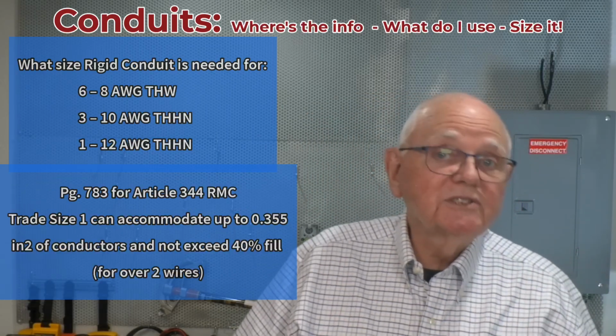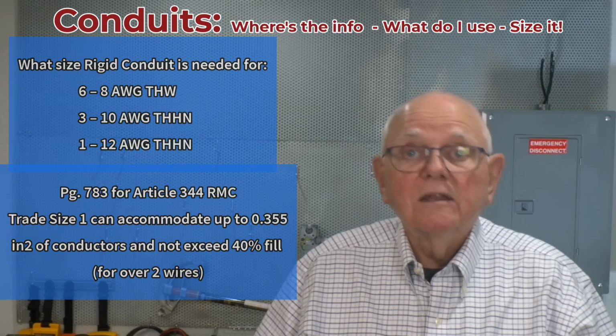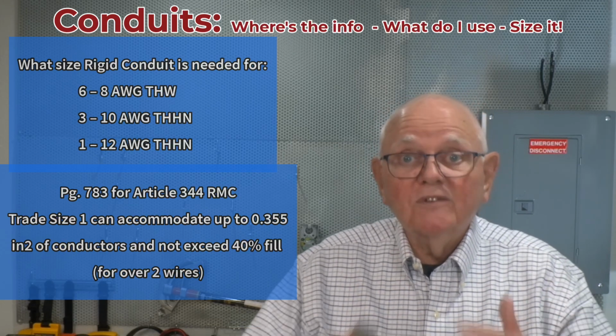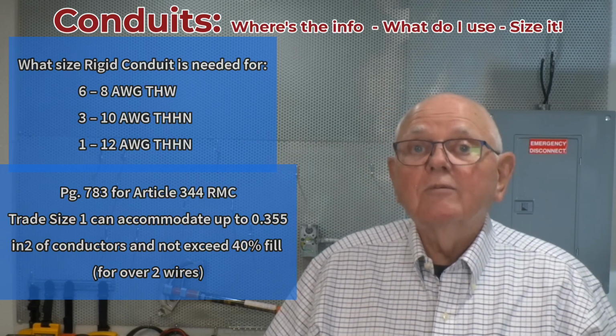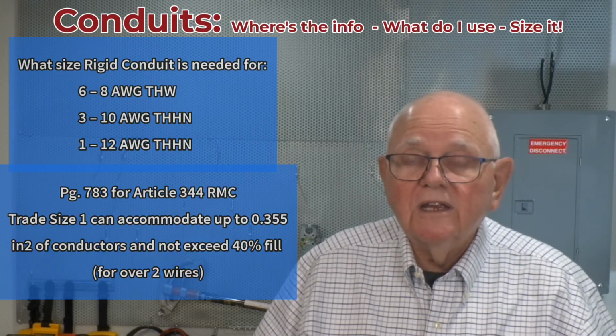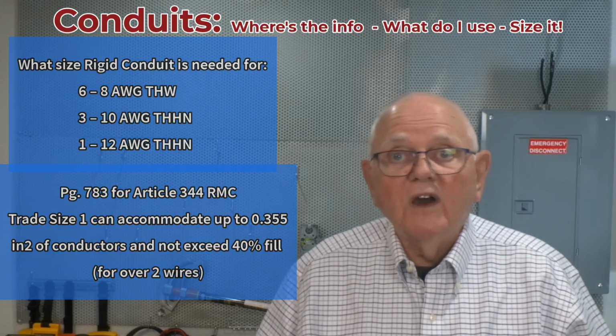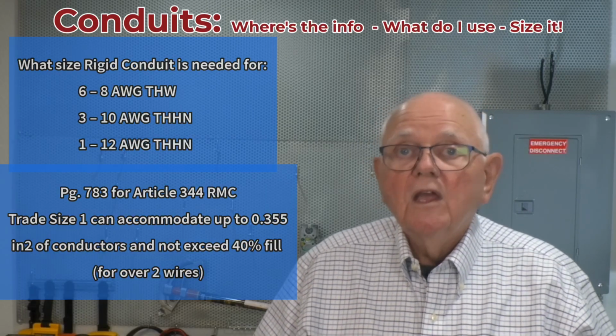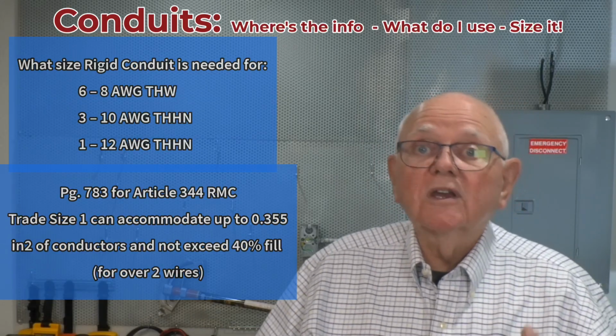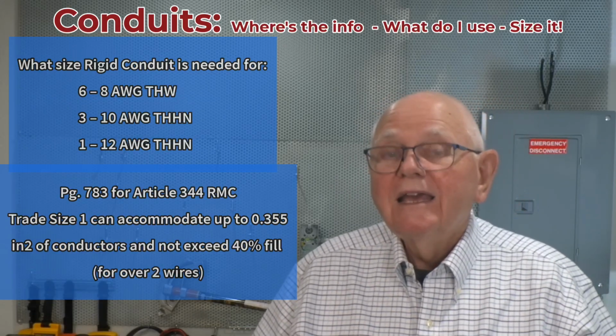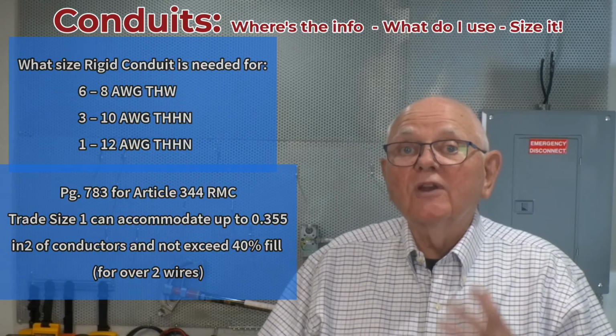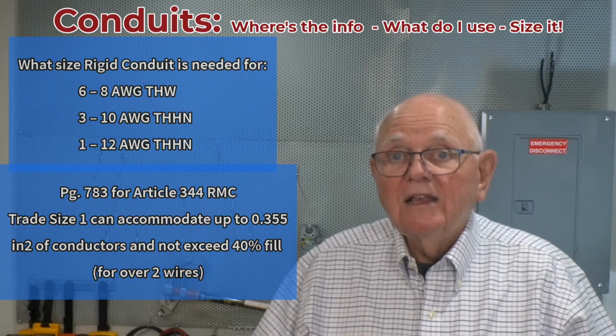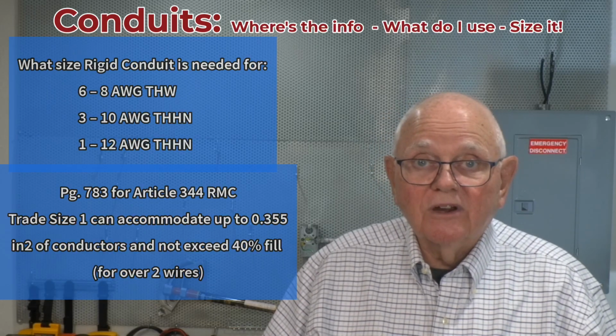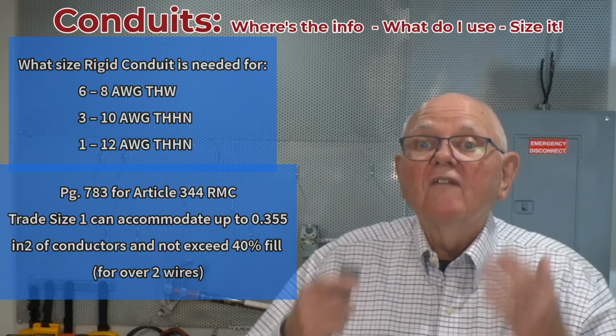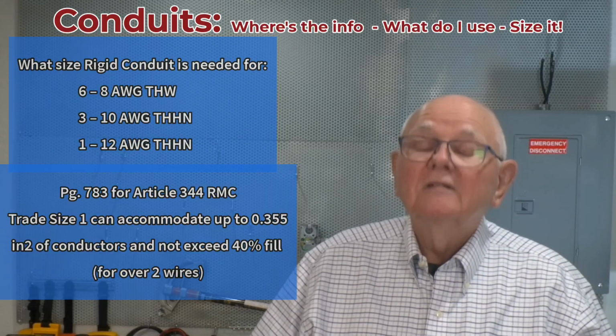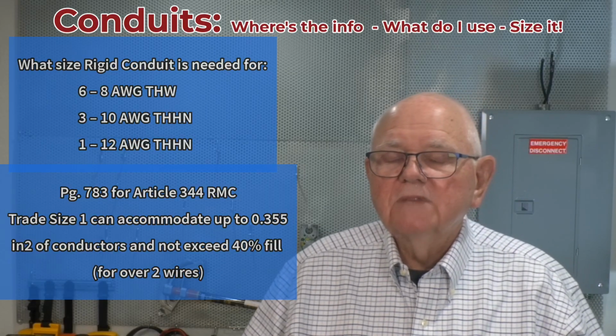Table 4 is on page 783, and table 4 is divided up by different types of raceways. So table 4 on page 783, article 344, you find rigid metal conduit. And sure enough, you take a look, and trade size 1 can accommodate up to 0.355 square inches of conductor material and not exceed 40% fill for over the 2 wires.